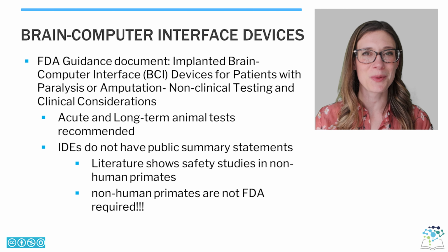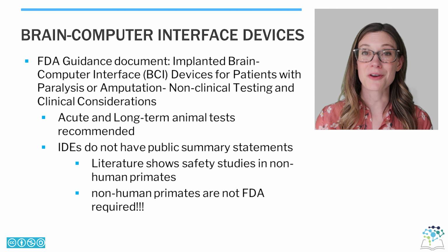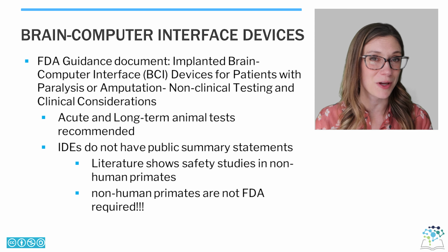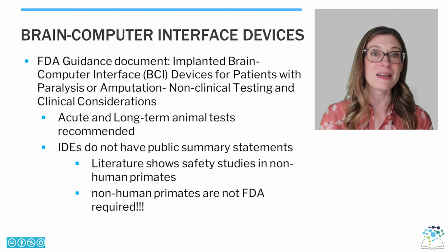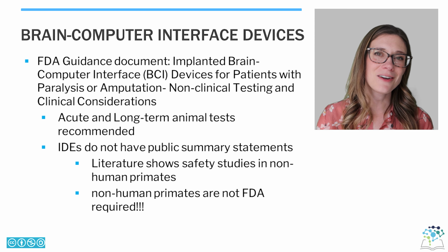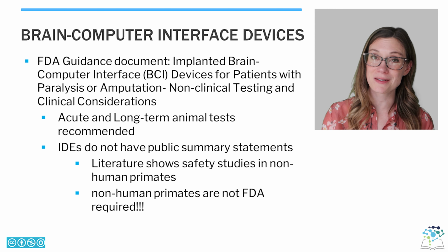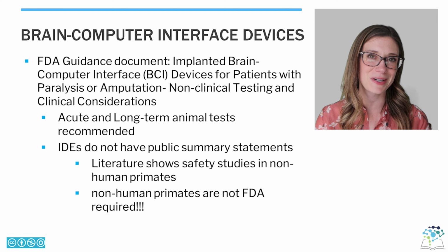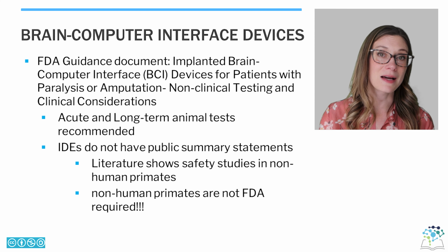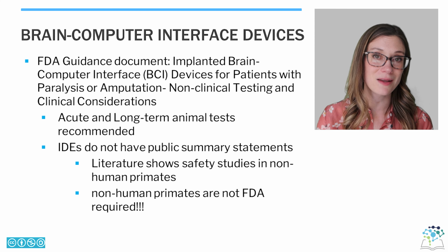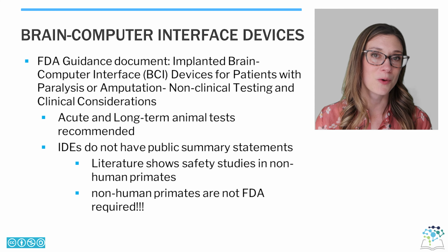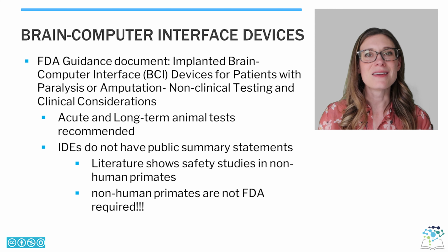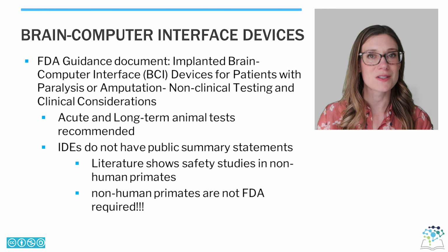The next case study that we'll be looking at is brain-computer interface devices. This is specific to implanted brain-computer interface systems, so an invasive technology. And here the FDA has produced another guidance document that could be helpful, similar to the guidance document for retinal prostheses. This document lays out some acute and long-term tests that the FDA would like to see for providing approval for this technology, but again, does not specify a species to consider.